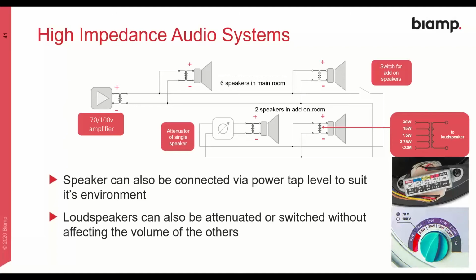Another way of attenuating a loudspeaker at installation time is by using a different power tap on the loudspeaker. So generally, loudspeakers for installation have multiple power taps. So this one I've shown here is a ceiling speaker, I think, and it has different power taps, for example, at 30 watt, 15 watt, 7.5 watt, 3.75 watt. So that really just changes the amount of the signal coming from the amplifier that will eventually get to the loudspeaker. So you can adjust that, for example, if you've got a 100-volt line going around the building and you have a bathroom where you need to put a loudspeaker, you could tap that down because you really don't want it to be too loud in that environment. So that's something you can do at installation time.